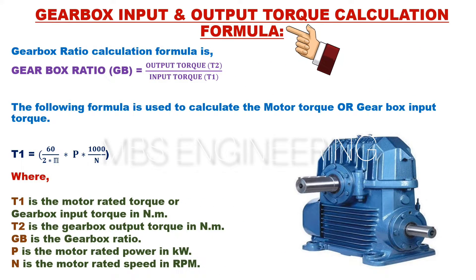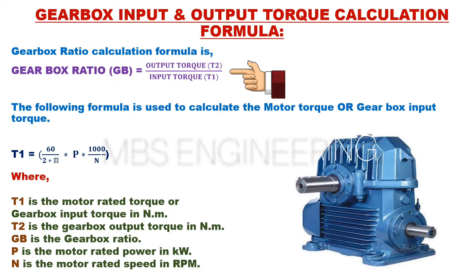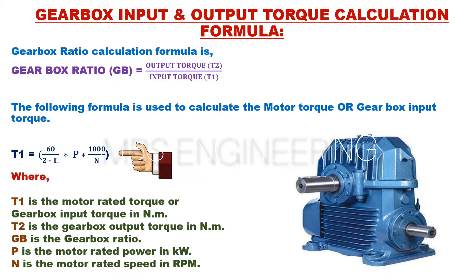We learn about how to calculate the gearbox input and output torques. The formula for calculating gearbox ratio is: Gearbox ratio GB equals output torque T2 divided by input torque T1. To calculate the motor torque or gearbox input torque, use the following formula: Input torque T1 equals 60 × P × 1000, divided by 2 × π × N.